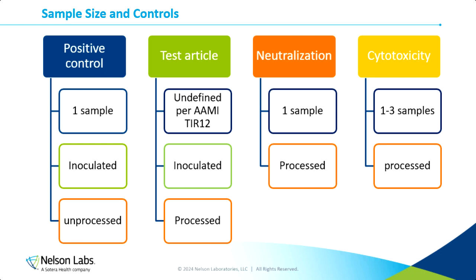We do typically see three test articles being the typical sample size used for disinfection validations. But you may need a larger test article sample size if you have a more complex device, like an endoscope or maybe a robotic device, just due to the complexity of that particular device. Again, this document doesn't require that you have a justification for the sample size used, but it is not a bad idea to have one. I would recommend having some sort of verbiage prepared for why you feel that the sample size used for your disinfection validation is appropriate.